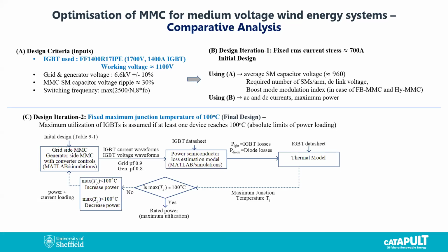Here is the design flow, showing how we optimize further in order to be able to compare the different MMC designs. We use the IGBT modules, which are more optimal for a two-level converter. But that was a starting point for us, and we wanted to use the same module and play around with different topologies, to see if we can get a better solution using the same power devices. Again, those power devices are not really optimal for the MMC.